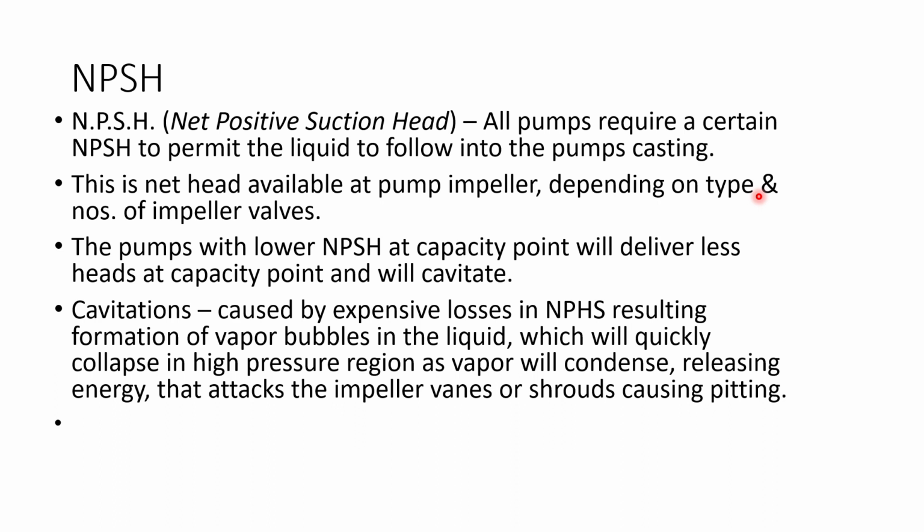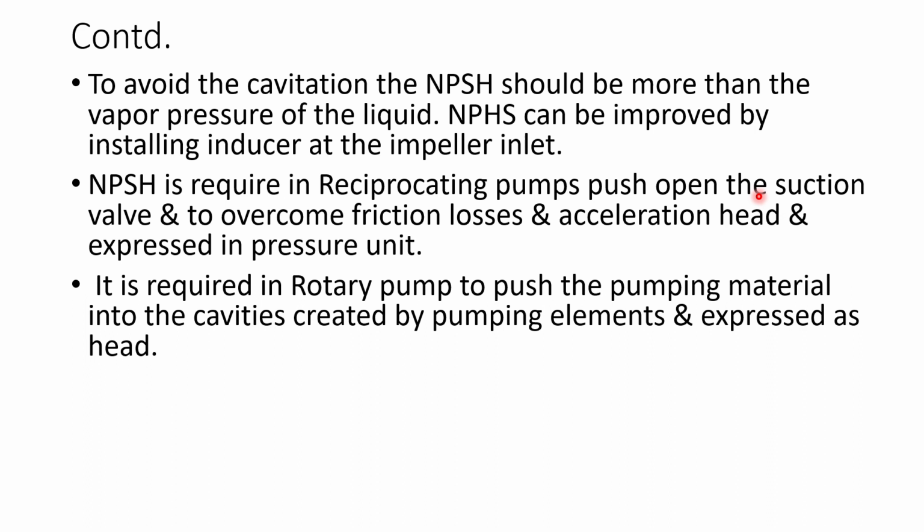What is cavitation? Cavitation is caused by excessive losses of NPSH, resulting in the formation of vapor bubbles in the liquid, which will quickly collapse in a high pressure region as the vapor condenses, releasing very high energy that attacks the impeller vane or shroud, causing pitting in the impeller. To avoid cavitation, the NPSH should be more than the vapor pressure of the liquid. NPSH can be improved by installing an inducer at the impeller inlet.